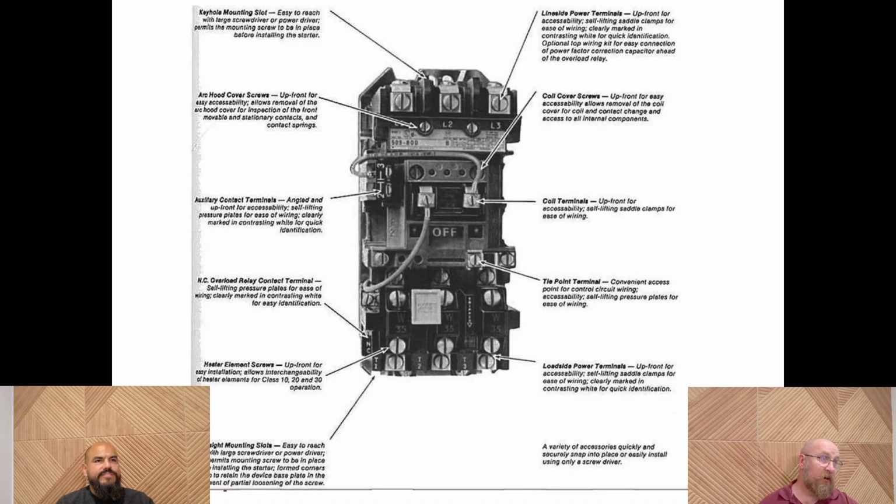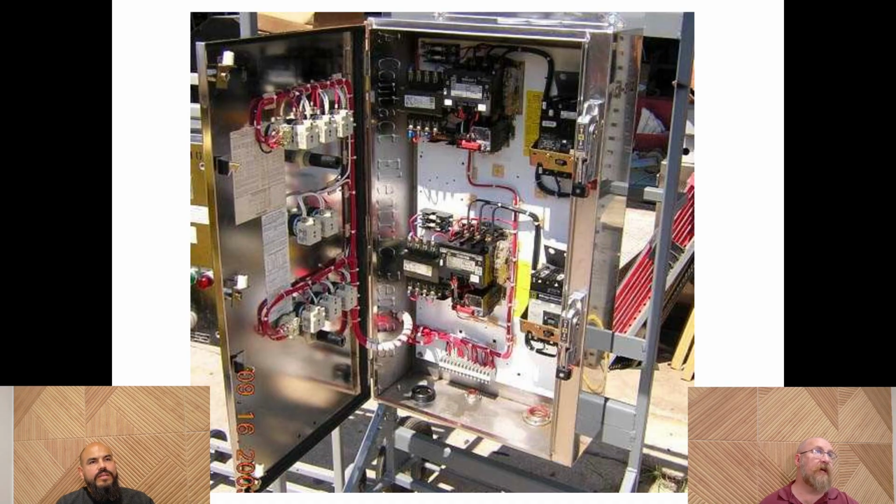So here's an example of how you would see these in a control cabinet. You'll see the panel-mounted stuff on the front that are the controls, and with all of this wiring, you're not going to be able to tell just by looking at it whether it's 2-3 wire forward reverse control, or what the control circuit is. You have to have a schematic. But this is really good wire organization for not having cable track in it. Those bends look really nice.